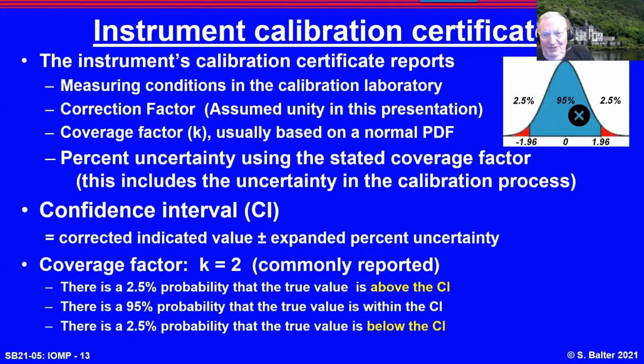Instruments come with calibration certificates. These, as medical physicists, we tend not to read as carefully as we should. The thing that needs to be looked at is what are the measuring conditions in the calibration laboratory. And occasionally there's shorthand, they're using an FH8 beam, et cetera. You need to understand what the measurement beams are for the calibration in terms of your use. It will give a correction factor under the calibration lab conditions. We're assuming it's unity, just to simplify life.